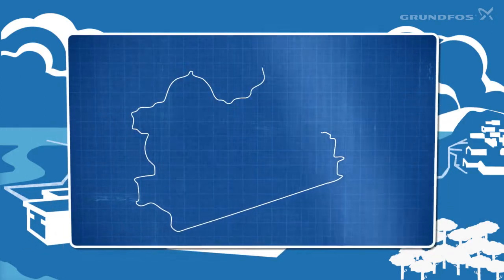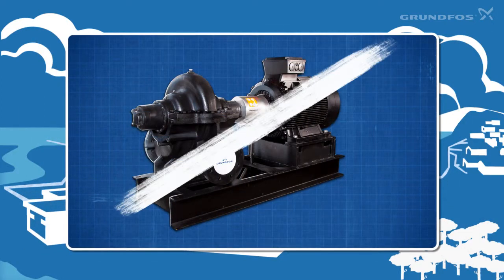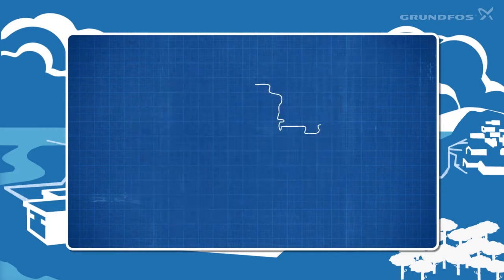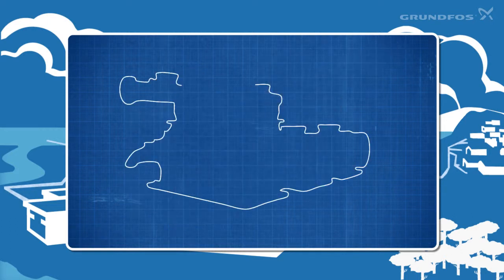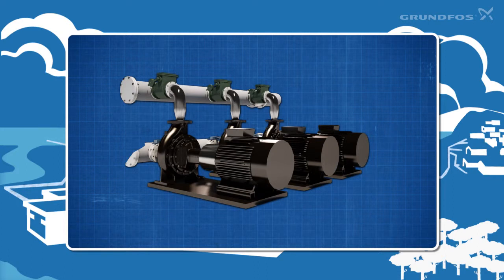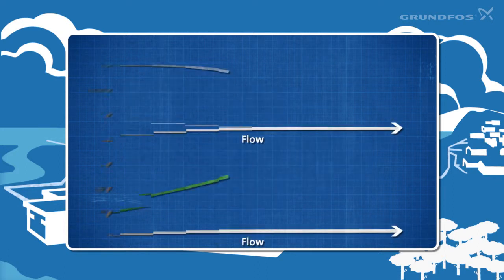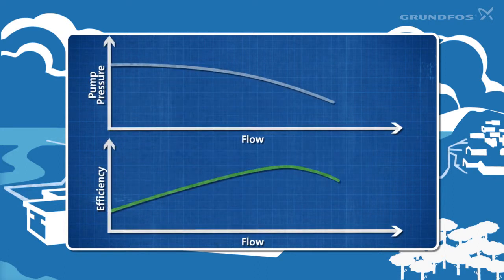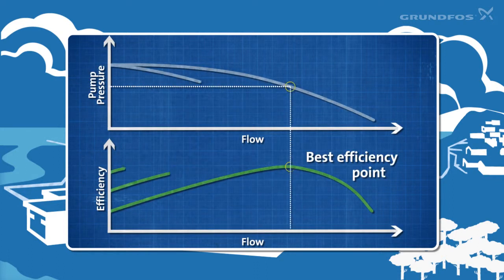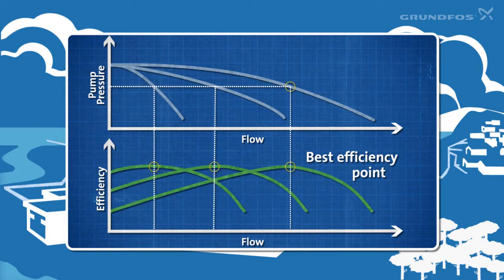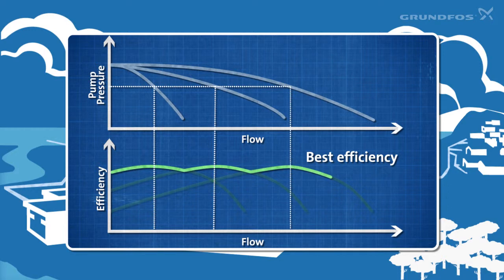Instead of a single large pump running at only one best efficiency point, you can use several smaller pumps, lowering energy consumption. Each of these pumps runs at its optimum efficiency and only when required. Combining multiple smaller pumps with intelligent pump control reduces up to 20% on energy consumption.